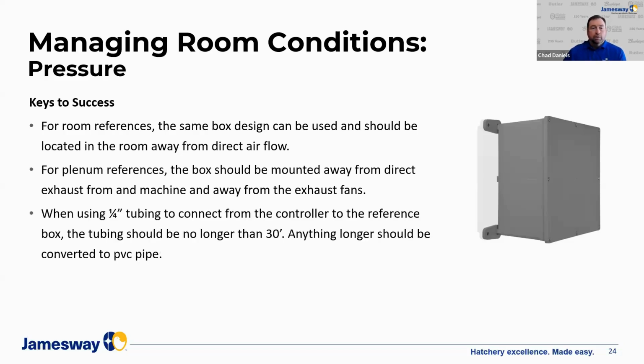When we usually see these systems installed, a lot of times we'll use 1/4-inch tubing, or very small plastic tubing, to connect from the controller to the reference box. Just keep in mind the tubing should be no longer than 30 feet. Anything longer should be converted to PVC. It's okay to use tubing on each end of that PVC to connect to the boxes. Just make sure that in between, if it's longer than 30 feet, you revert to a 1/2-inch or 3/4-inch PVC conduit.